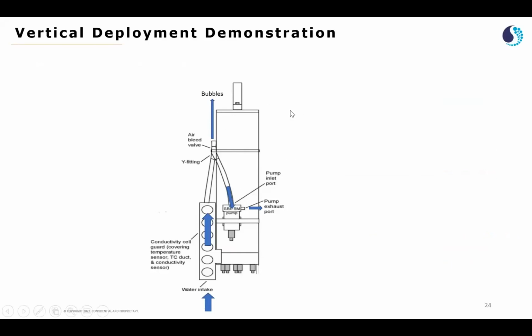Here, I will be showcasing what a vertical deployment would look like. So in the plumbing slide, we did talk about how the water flows through the entire system. So let's imagine that the 19 plus system is in vertical configuration. We're going to put this in a tank for a test deployment. The water goes through the water intake. It goes through the conductivity temperature probe. The water then flows to the air bleed and Y fitting. And this is where you will start observing bubbles coming out of the air bleed.